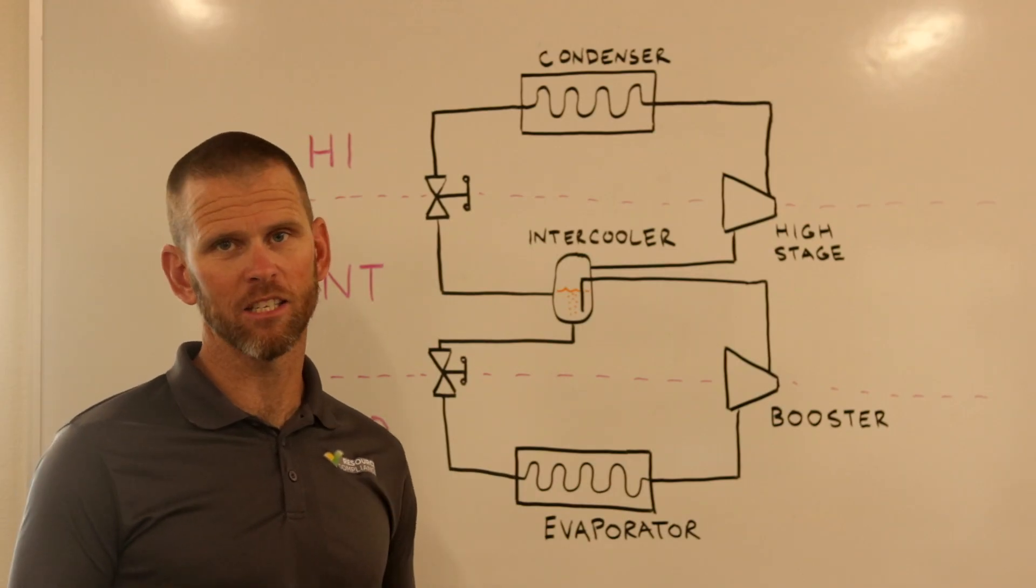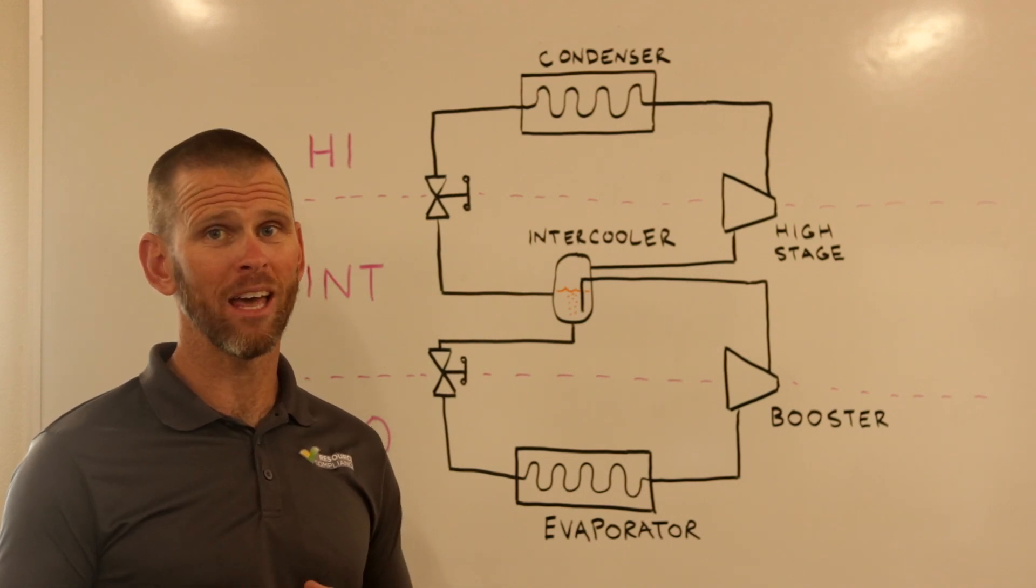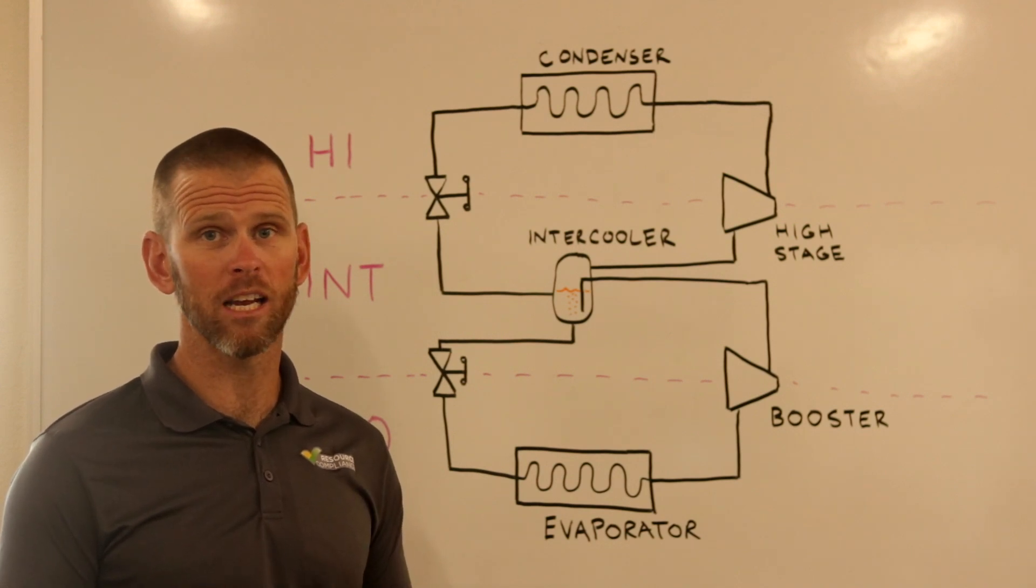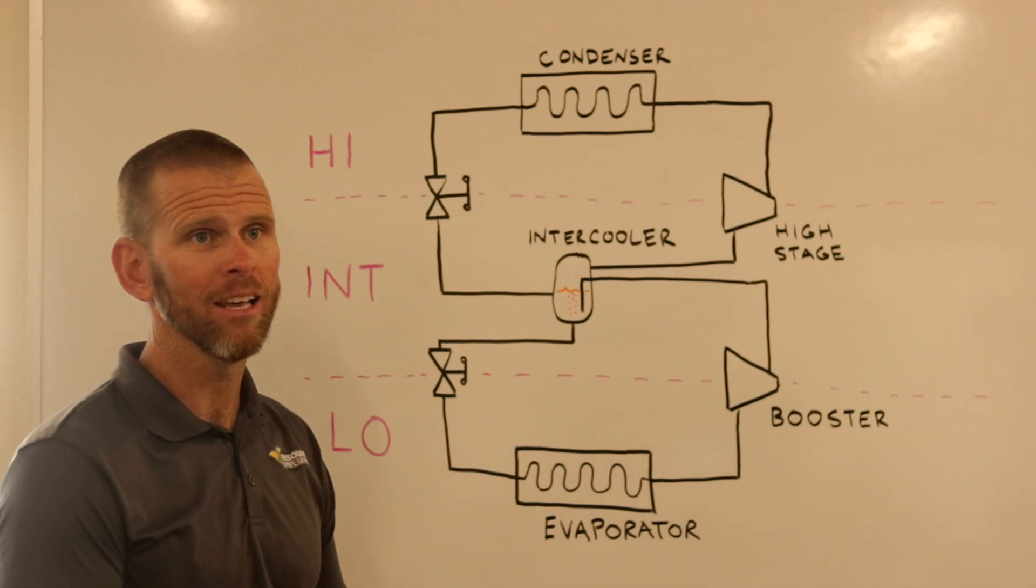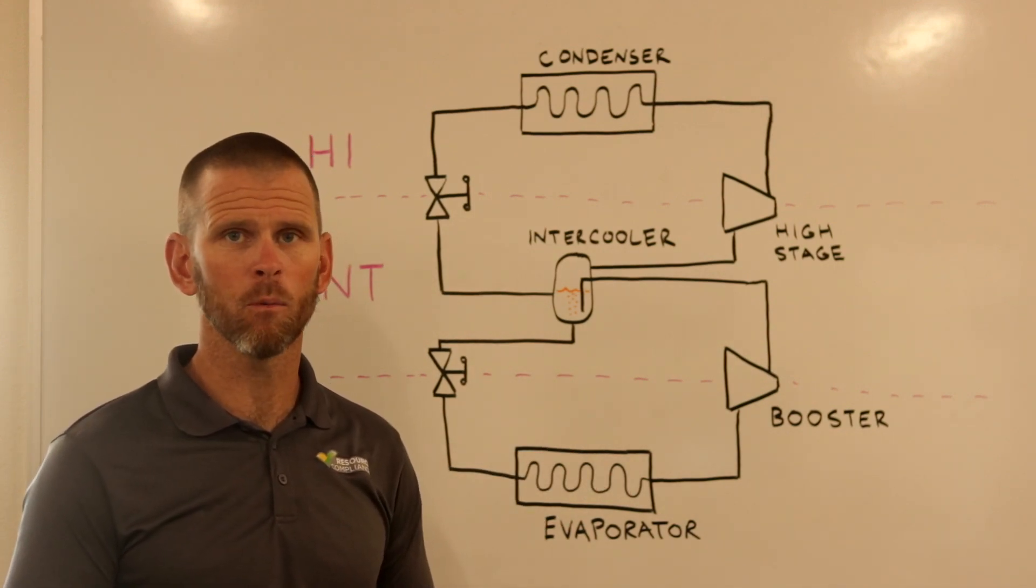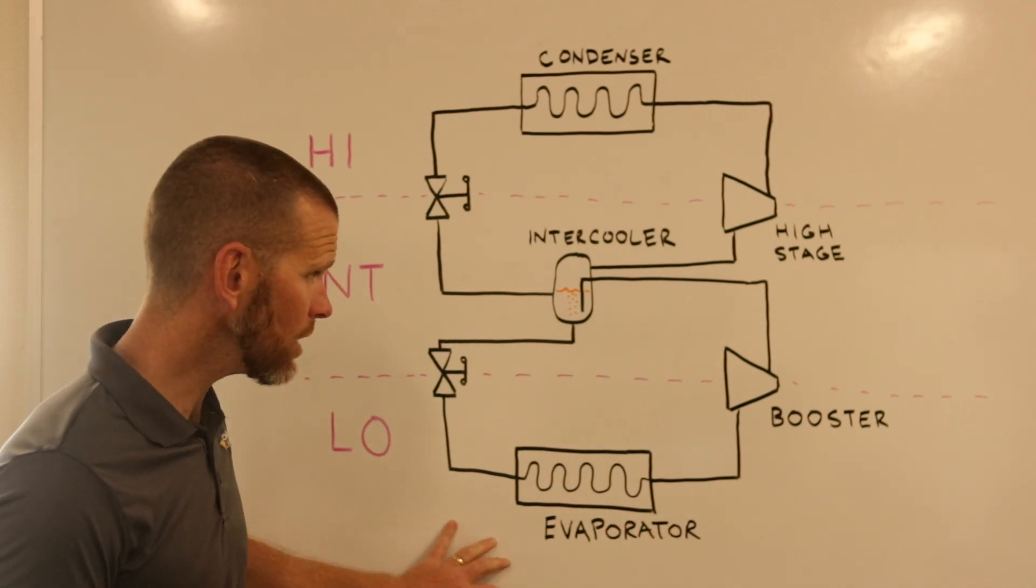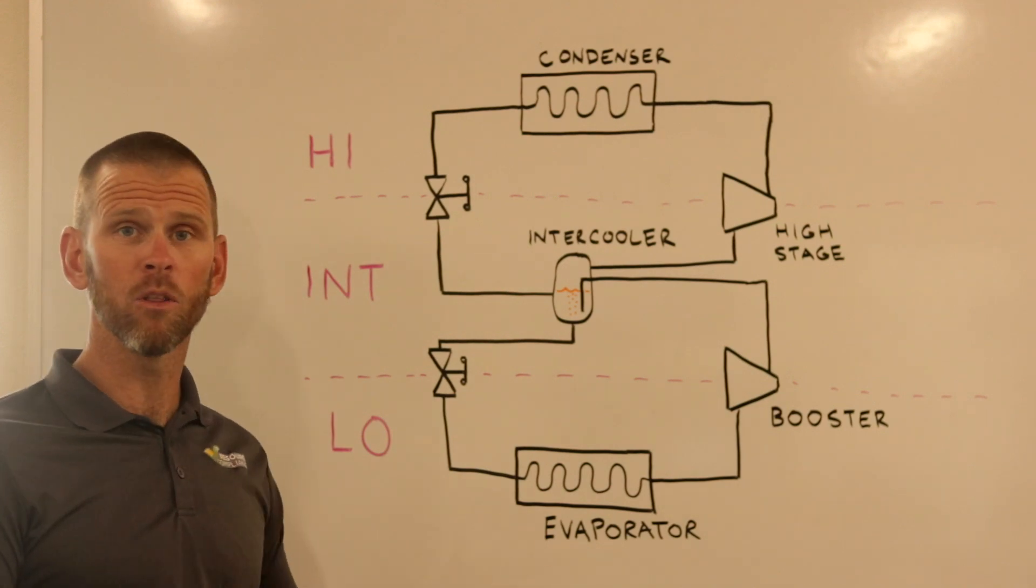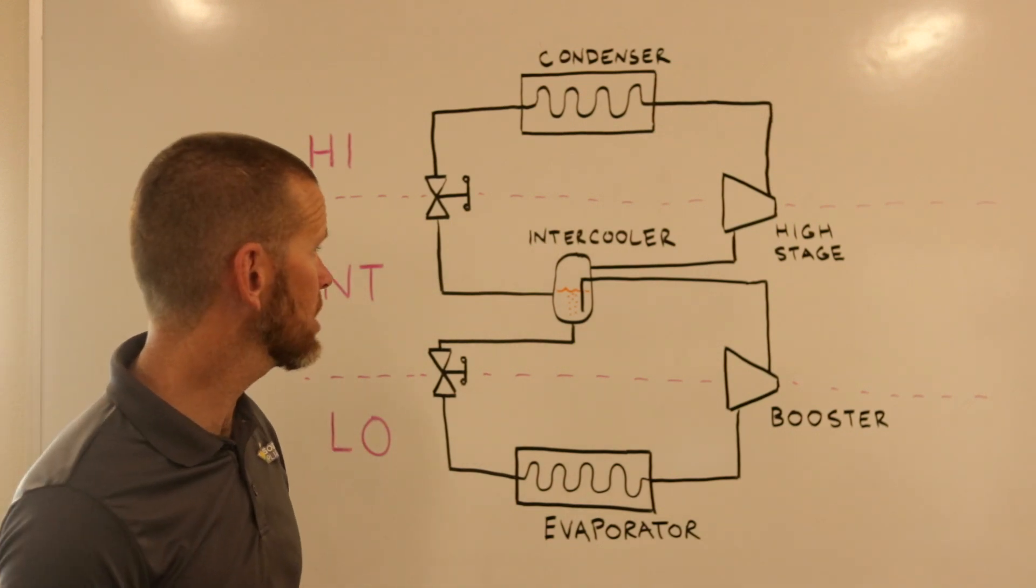So let's talk about two-stage systems. Due to the discharge temperature that results when you try to run a freezer system in a single stage of compression using ammonia, we have to go to a two-stage system, because high discharge temperatures are simply unacceptable once they get over a certain level. In a two-stage system, a simple diagram is depicted here on the whiteboard. There's a lot here that we're already familiar with because we've gone over it previously, but let's walk through this.